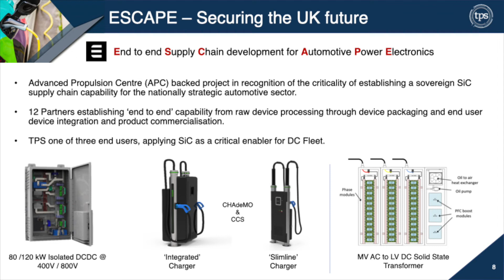So here is MV fleet. Here's what we talked about, the solid state transformer feeding the chargers. It starts to get quite complicated. Solid state transformers are complicated by their very nature, and we have 3 strings of converters. The direct current transformer is the clever bit. That basically takes DC, converts it to high frequency AC, and then converts that high frequency AC across a transformer back to DC that we can use. And those sections are comprised of lots of strings, and the Escape technology is really helping us develop the MV to LV cell within that string, okay? And for this solution, there's 36 of them. We are bound to use 1200 volt devices, and Dave after me is going to talk a little bit about going to higher voltage devices, which can really help the viability of solid state transformers.